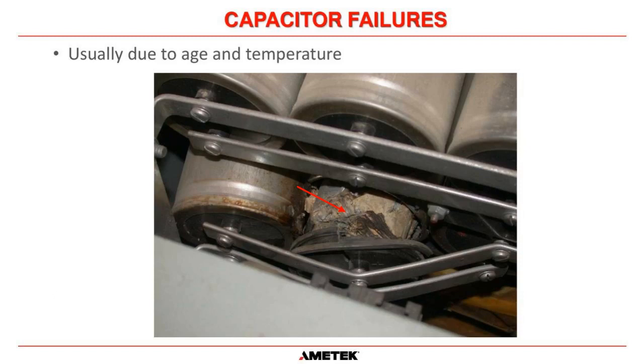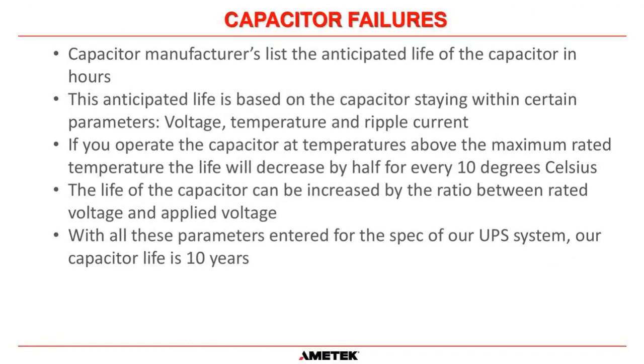You can see on this capacitor here, there has been some contamination due to the capacitor failing, and that can get on control boards and go all over the UPS as well. So capacitor failure is something you really, really want to stop. And obviously it's going to stop the operation of the UPS. So capacitor manufacturers list the anticipated life of their capacitors in hours on their datasheet. And the anticipated life is based on certain parameters. And the three main parameters are voltage, temperature, and ripple current.